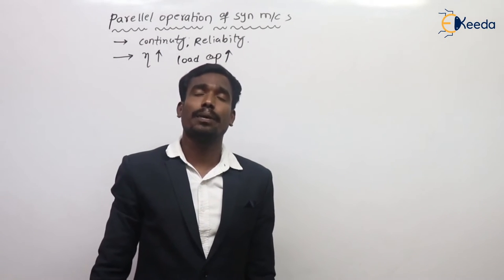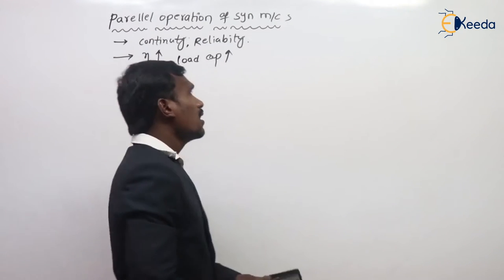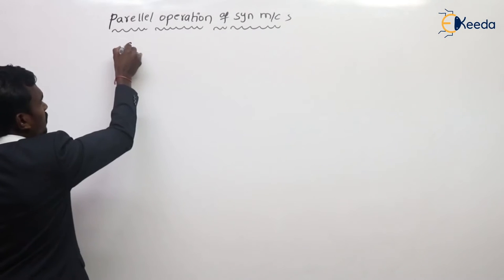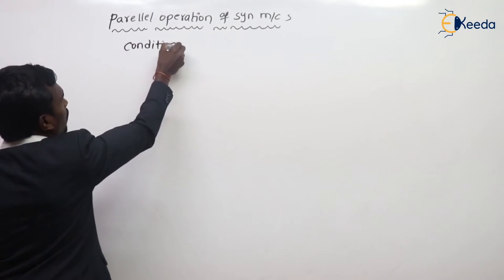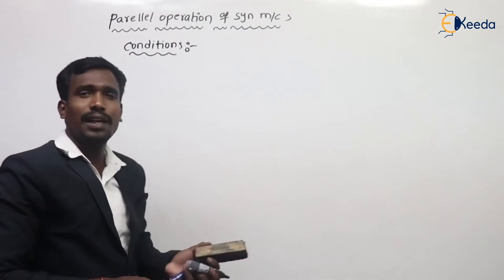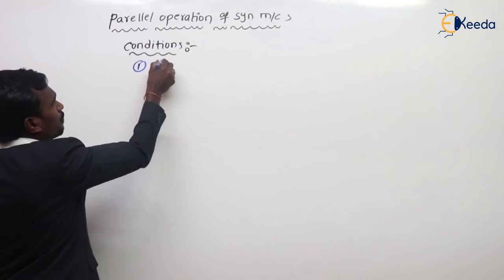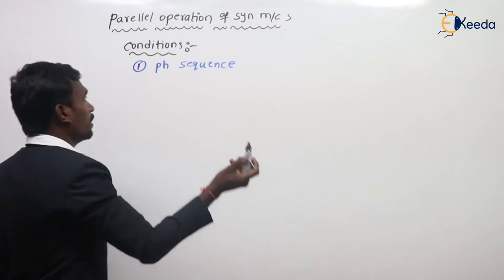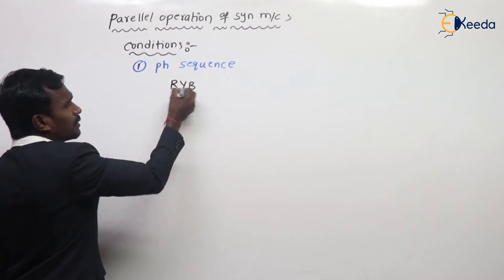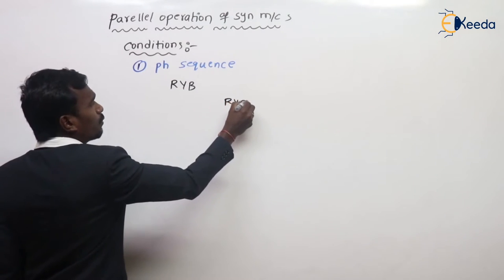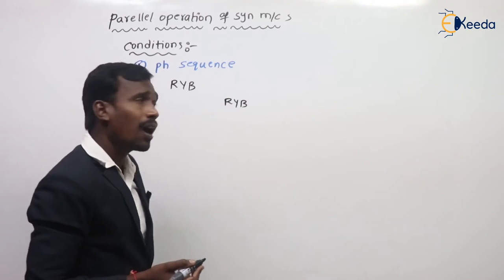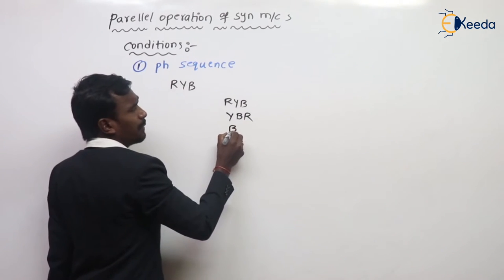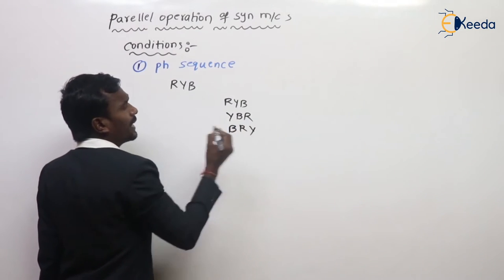Now, what are the conditions for parallel operation of synchronous machines? The first condition is that phase sequence should be same. For example, if one machine's phase sequence is RYB, then the next machine's phase sequence should also be RYB.